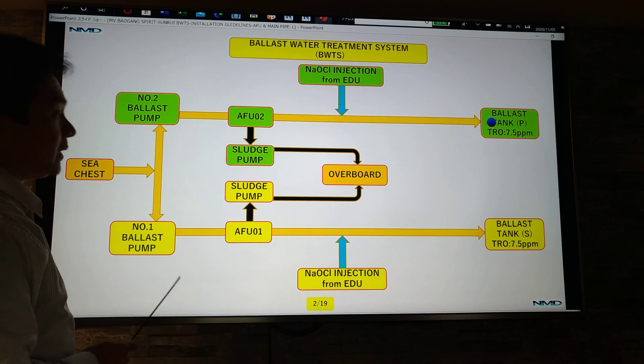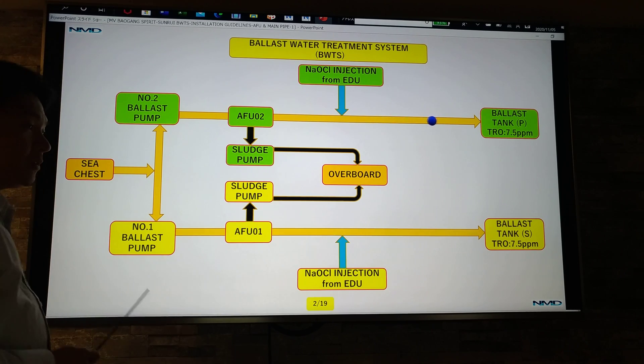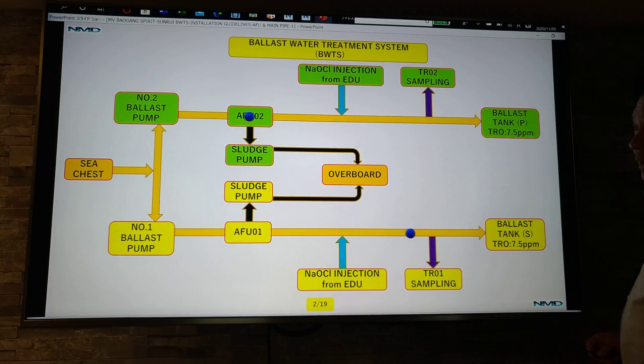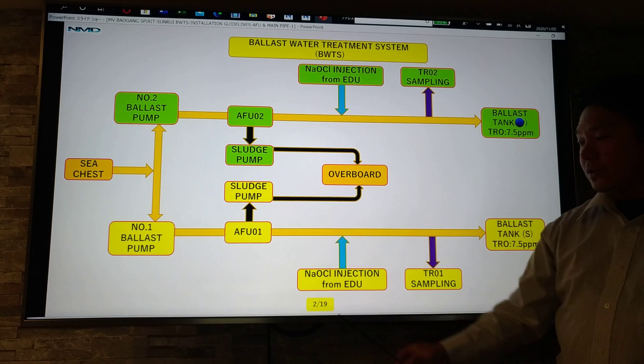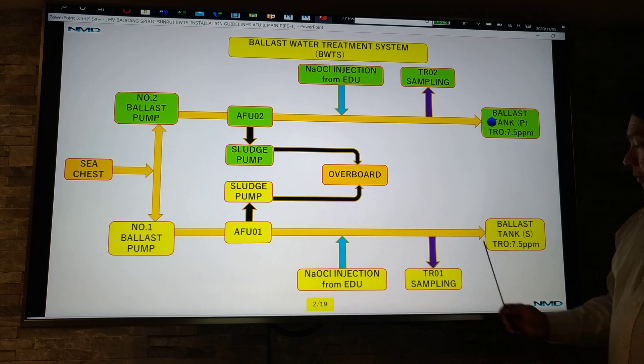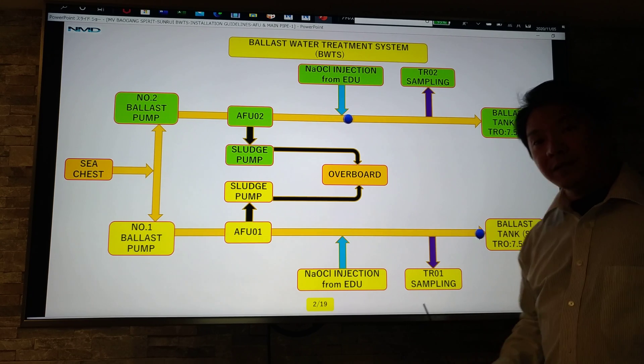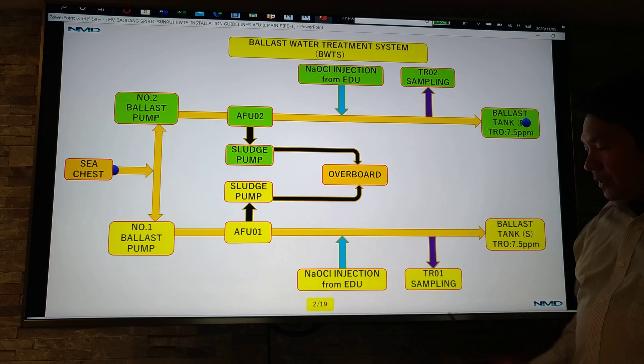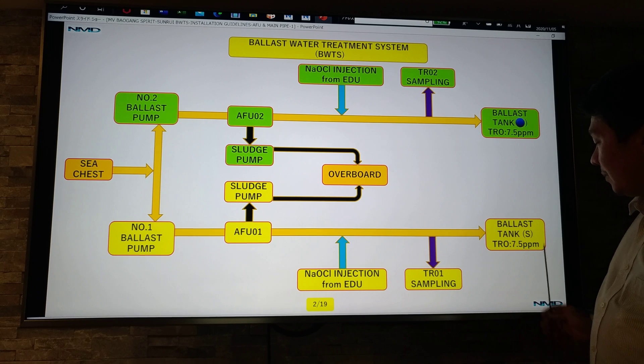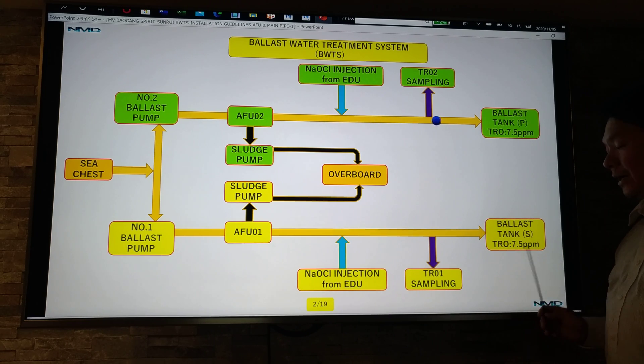Using the ballast water treatment system, we have two systems: filtration and injection of sodium hypochlorite from the EDU, both on starboard side and port side. We also use TRO sampling. You have to maintain that the sea water inside the ballast tank has a TRO of 7.5 ppm. If the TRO is less than 7.5 ppm, the EDU will inject more sodium hypochlorite to maintain the ballast tank at 7.5 ppm.